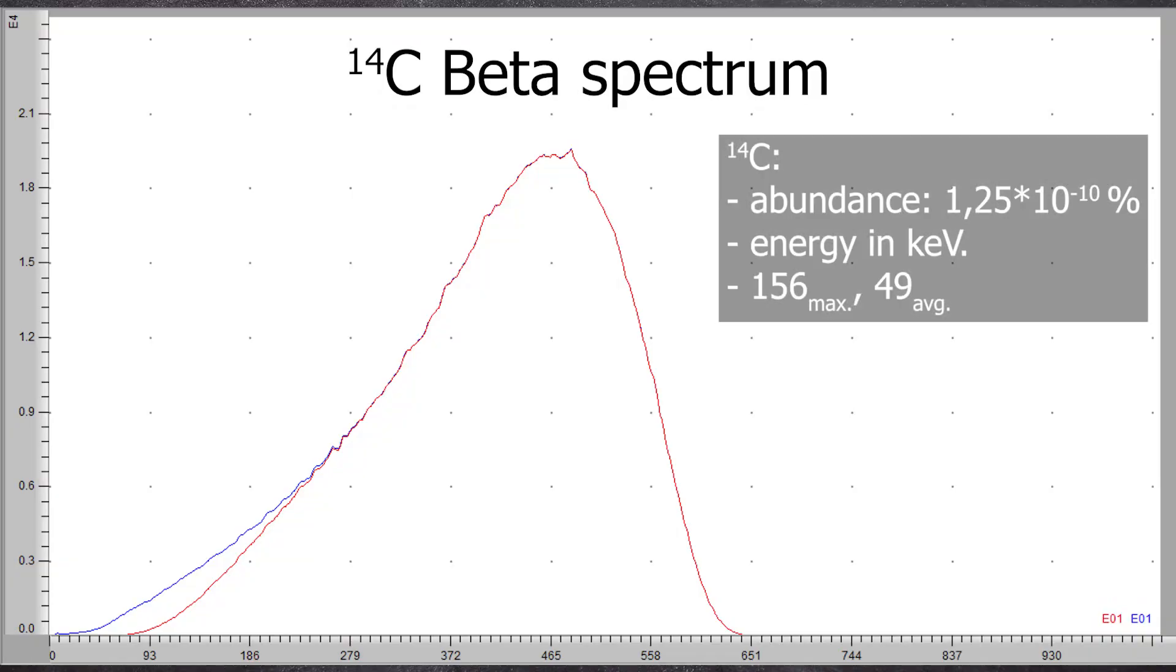When all three detectors simultaneously register light, we call this a triple coincidence, a clear indication of a radioactive decay. These triple coincidences are particularly evident with carbon-14, which has a maximum beta energy of 156 kilo electron volts. The energy is sufficient to achieve good triple coincidences.